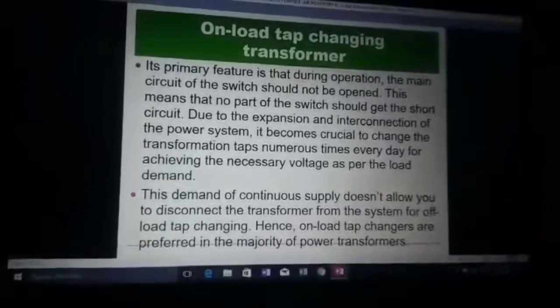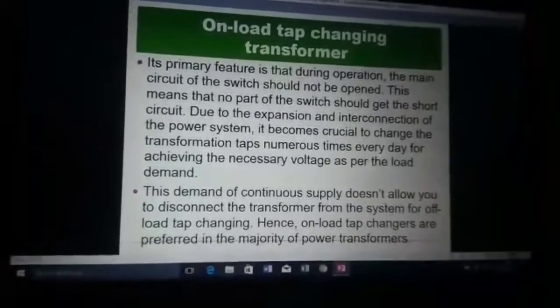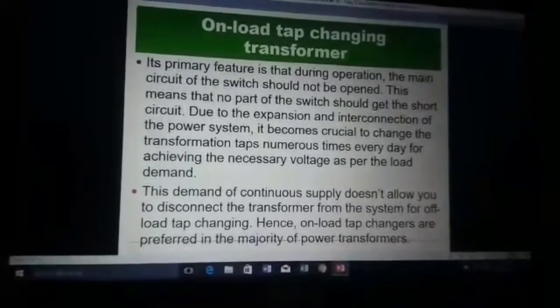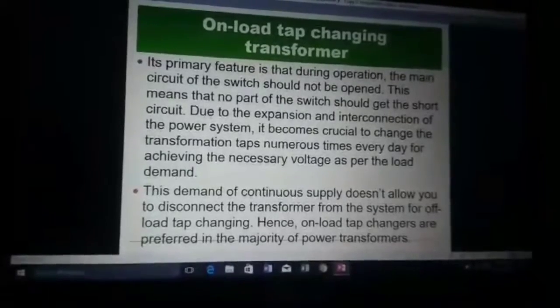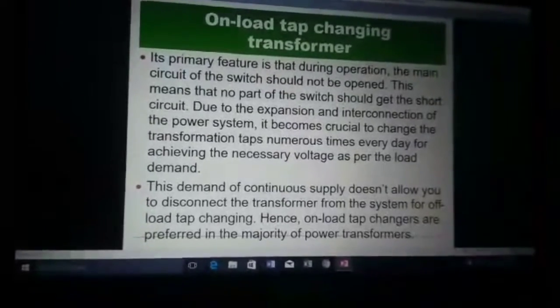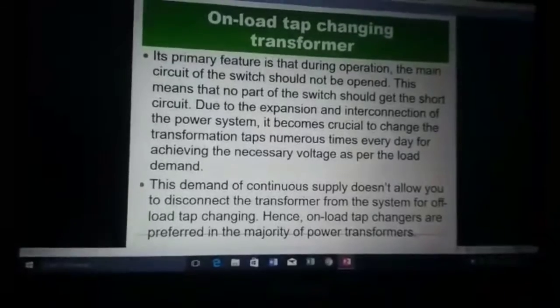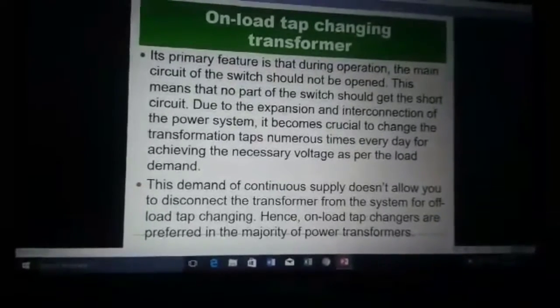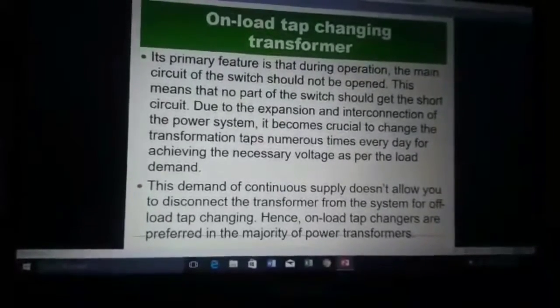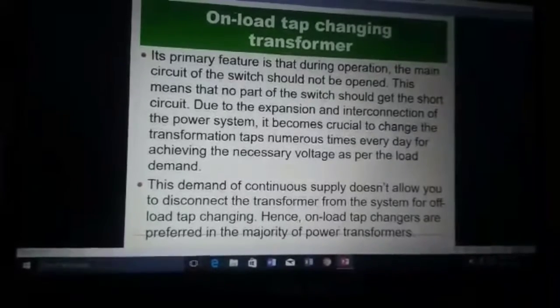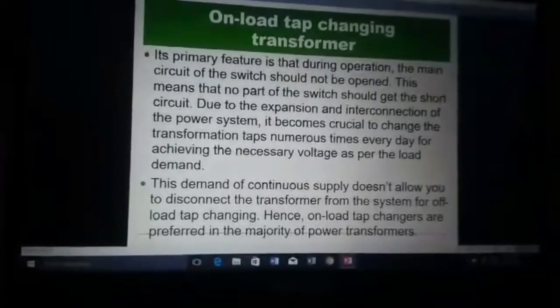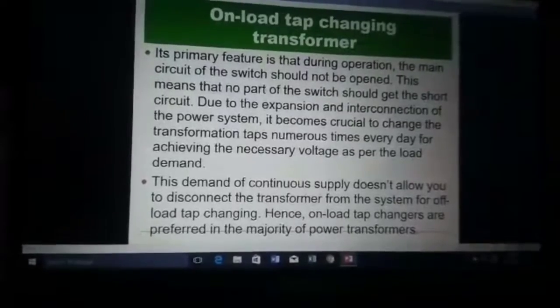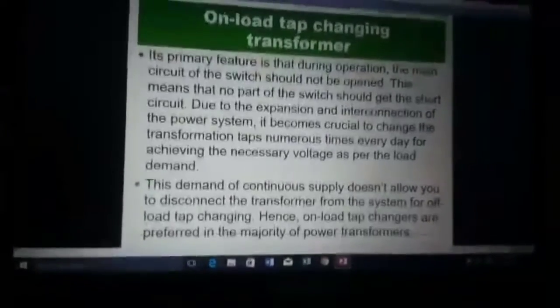Due to the expansion and interconnection of the power system, it becomes crucial to change the transformation taps numerous times every day for achieving the necessary voltage as per the load demand. This demand of continuous supply doesn't allow you to disconnect the transformer from the system for offload tap changing. Hence, onload tap changers are preferred in the majority of power transformers.